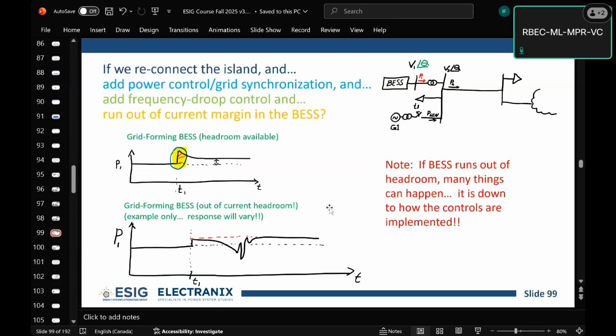It's very hard to do, and what happened is they ended up doing a lot of tuning on their controls in that environment and against those tests to try and make that fault ride through robust. When you move to mainland US and you're in stronger systems and you put a fault on the system, they seem relatively trivial for these plants to ride through at this point. So a lot of them have been working really hard on really challenging systems. Seems to be helping them in the good systems.